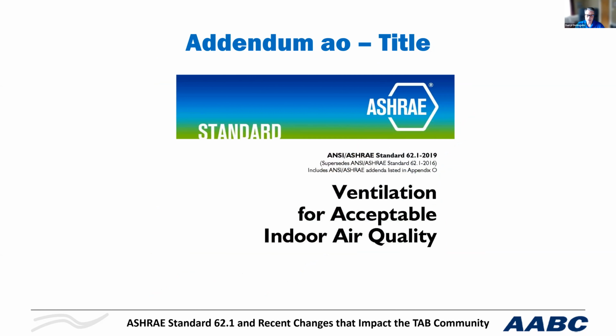So speaking of the past, the first change I'm going to talk about is a change to the title. This title has been the same since 1981 when it changed for ventilation for acceptable indoor air quality. However, now the new title is ventilation and acceptable indoor air quality. Although this appears insignificant, it basically reflects how the standard has evolved. Ventilation isn't the only way to maintain indoor air quality. It encompasses everything, including the design, the installation, the control in the systems, the selection and operation of the right components in the systems, and then the activities such as TAB, commissioning, and maintenance. So all of this makes for indoor air quality.